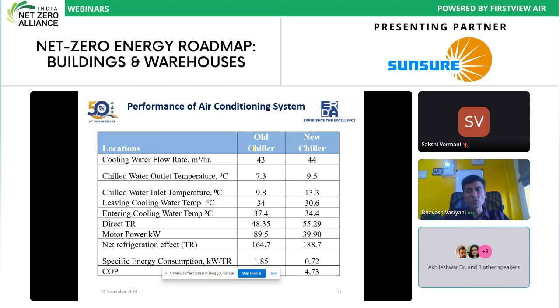Like in this case, there were two chillers. One is old and another is new. So here, chilled water and cooling water flow rate and chilled water temperature difference give the direct TR developed. So kilowatt per TR is calculated for this old and new chiller. You can see, as expected, the old chiller is consuming higher, double that of the new chiller. So it is not only a case of aging, that this is new so performing well and this is old so performing badly, but we can find out the areas due to which this specific energy consumption is getting affected, and then rectification of those can optimize its performance to near, or somewhat poorer than, the new chiller.